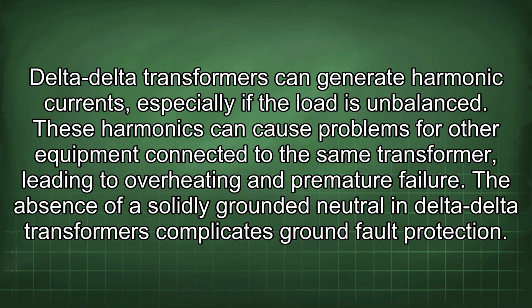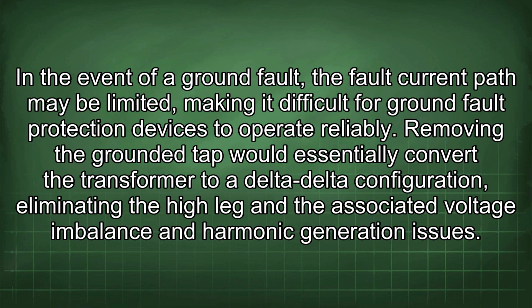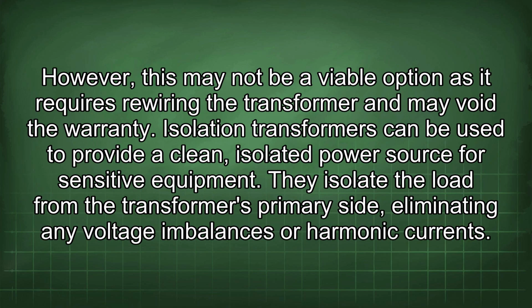The absence of a solidly grounded neutral in delta-delta transformers complicates ground fault protection. In the event of a ground fault, the fault current path may be limited, making it difficult for ground fault protection devices to operate reliably. Removing the grounded tap would essentially convert the transformer to a delta-delta configuration, eliminating the high leg and the associated voltage imbalance and harmonic generation issues. However, this may not be a viable option as it requires rewiring the transformer and may void the warranty.